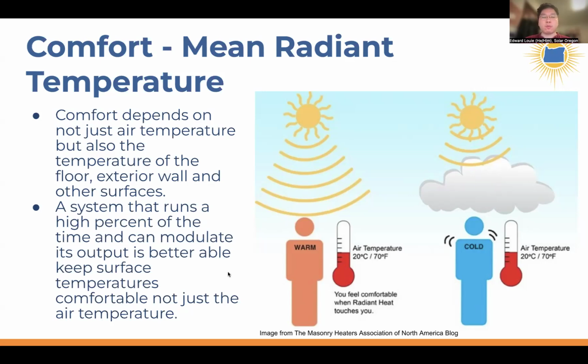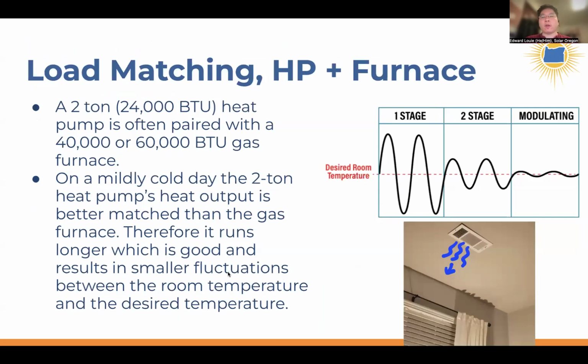So this is a very important concept, and I alluded to the idea of runtime being a link to this comfort. One thing to note is that a dual fuel system will generally give you a higher degree of comfort. And the reason is because a dual fuel system typically has a heat pump that has a significantly lower heat output than the gas furnace. That's not a bad thing. Oftentimes, the gas furnace is quite oversized for the home's heating load, or the amount of heat it takes to keep that home comfortable.